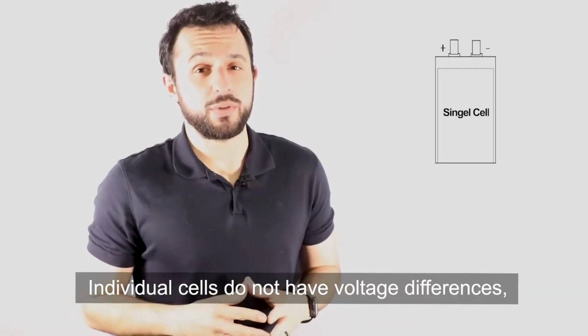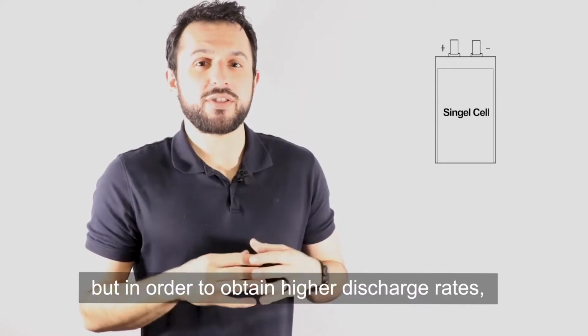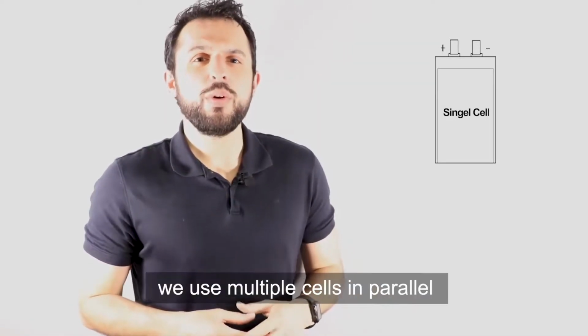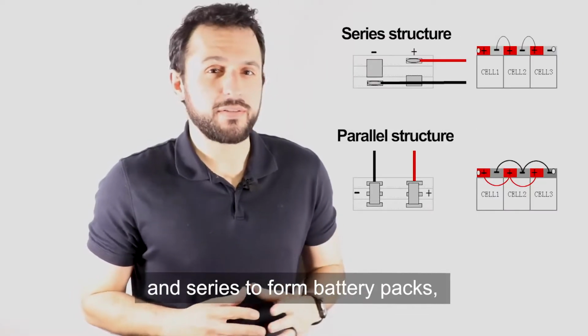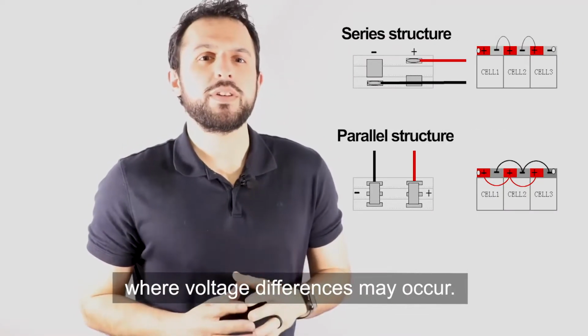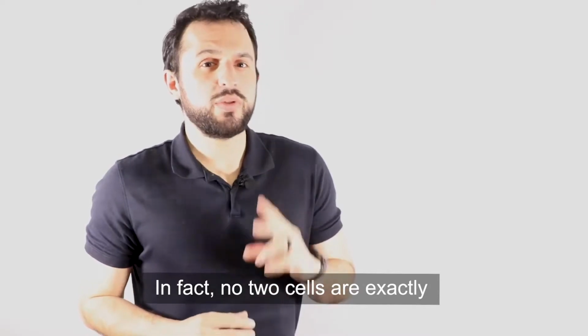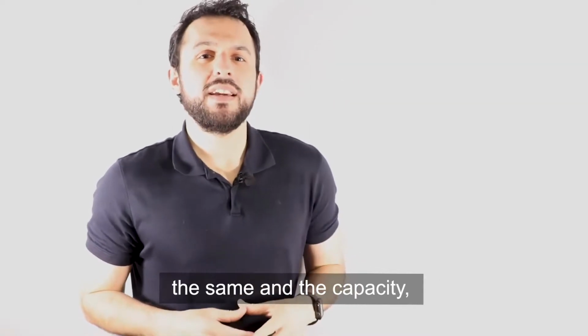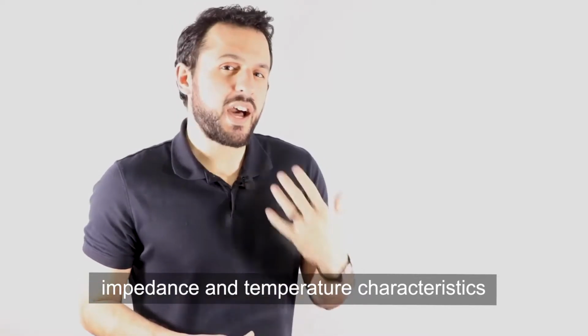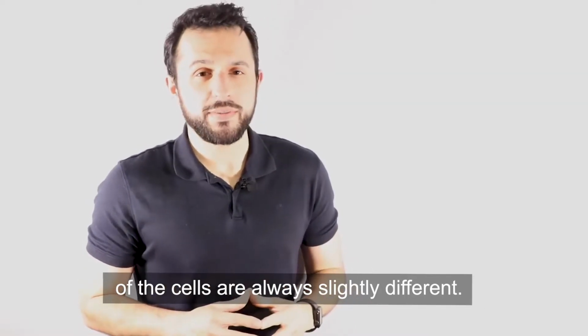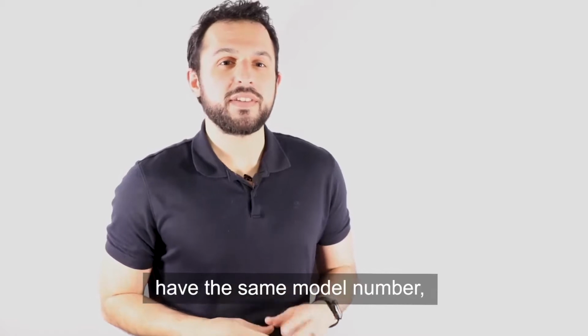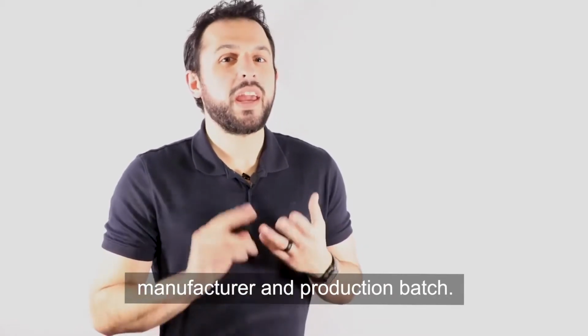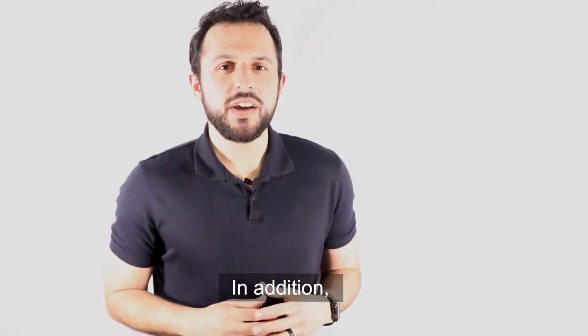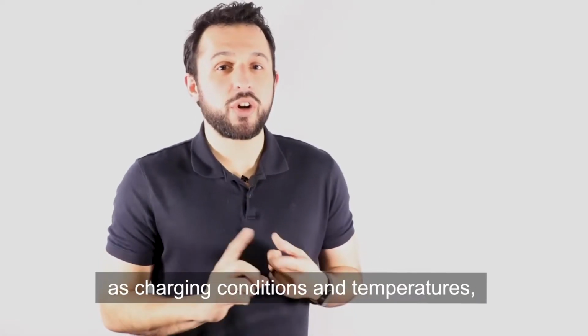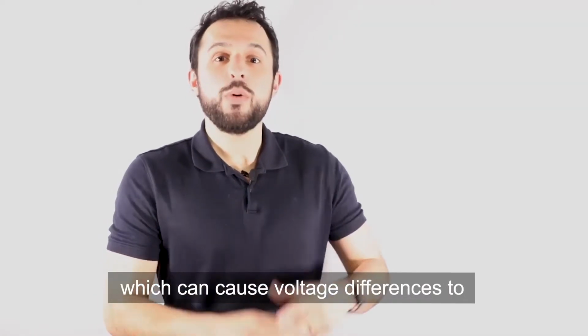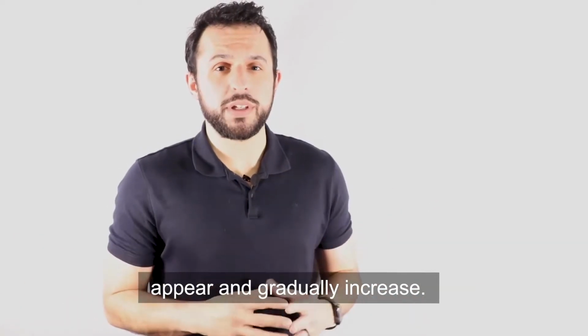Individual cells do not have voltage differences, but in order to obtain higher discharge rates, capacities, etc., we use multiple cells in parallel and series to form battery packs, where voltage differences may occur. In fact, no two cells are exactly the same, and the capacity, impedance, and temperature characteristics of the cells are always slightly different. This is true even if the batteries have the same model number, manufacturer, and production batch. In addition, the battery pack is affected by factors such as charging conditions and temperatures, which can cause voltage differences to appear and gradually increase.